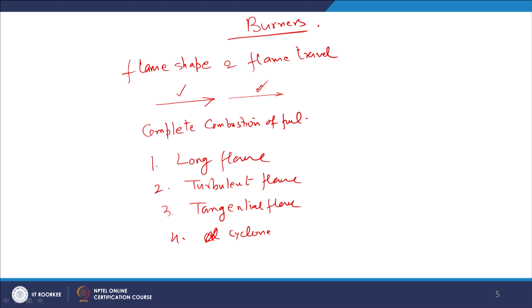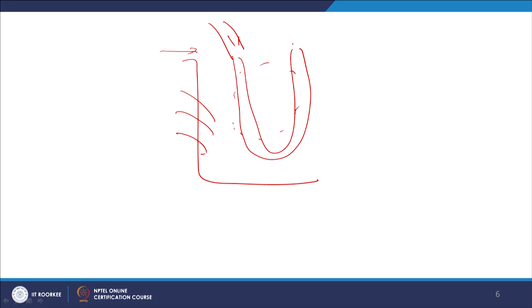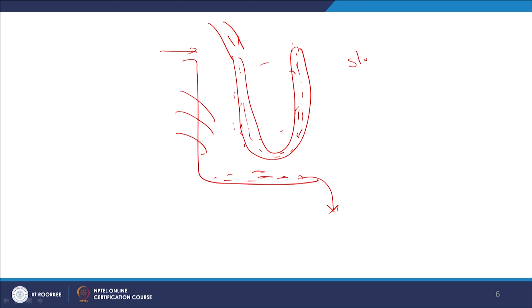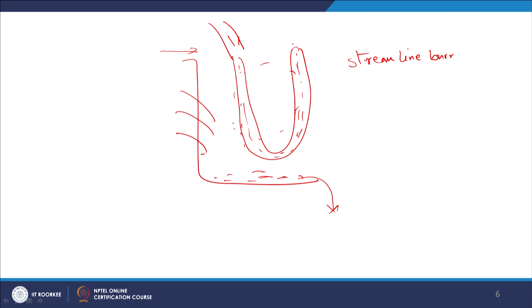In the long flame burner, suppose it is something like this, and your primary air is coming from this side, and there is a tertiary air also, because secondary air is coming from this side, and combustion is taking place here, right? The flame of the burner is sometimes called a U flame burner also. This happens when the coal has low volatile material. When the coal is low volatile, this type of burner is recommended. Here the formation of ash takes place, and subsequently ash can be drained off or removed from the system. So this is the long flame type, or U flame type, and it is also called a streamline burner, right?